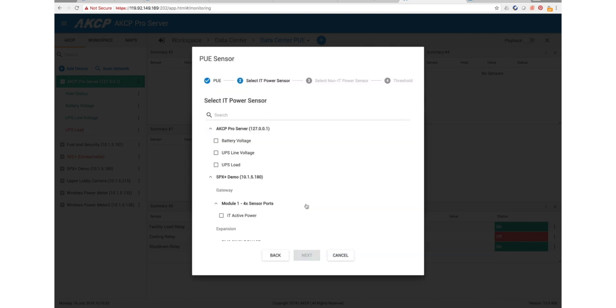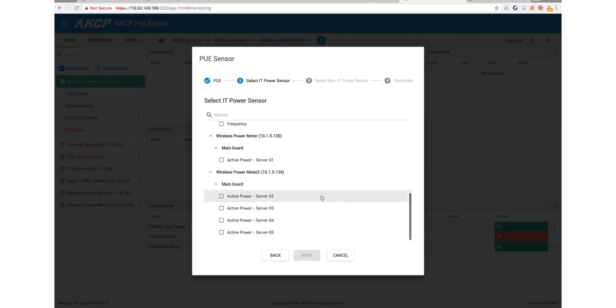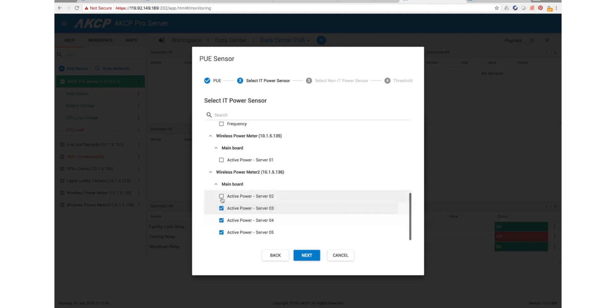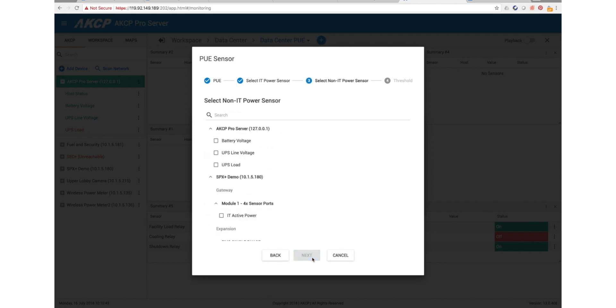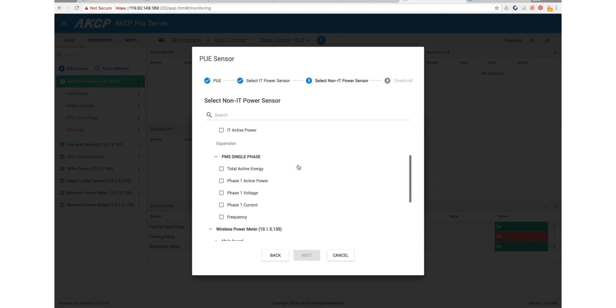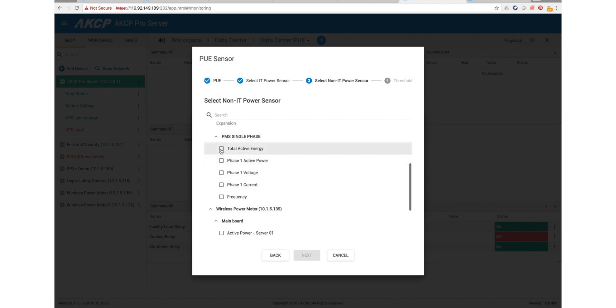Now we need to select our IT power sensors. I've got several sensors here which are our active power for our IT load. This is the active power for server 1, 2, 3, 4, and 5. And now we need to select our non-IT power. That's going to be our total active energy phase 1 active power.